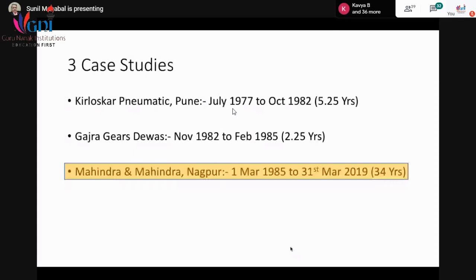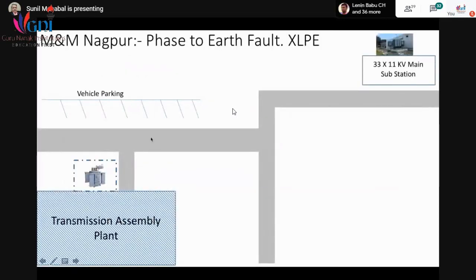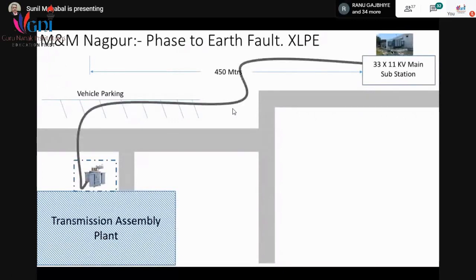Then this is vehicle parking. This is the road. This is the service road inside the factory. And then there is a 33 by 11 kV main substation. From here, one cable was laid. This distance was around 450 meters. It was 450 meters away from the substation. And a cable was laid a few years ago to connect to the RMU, which we recently added. When the 33 kV came, we added the RMU also, the ring main unit.